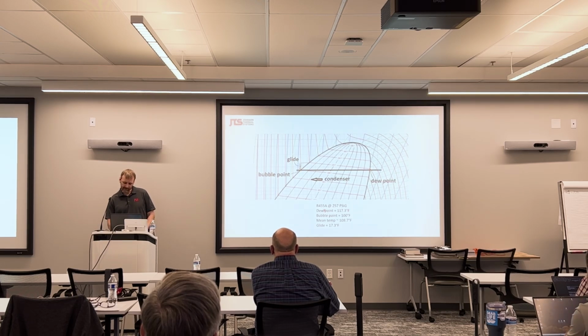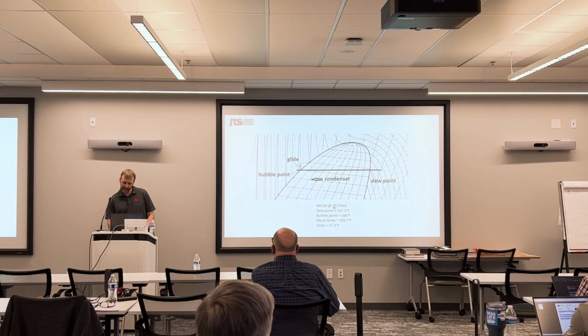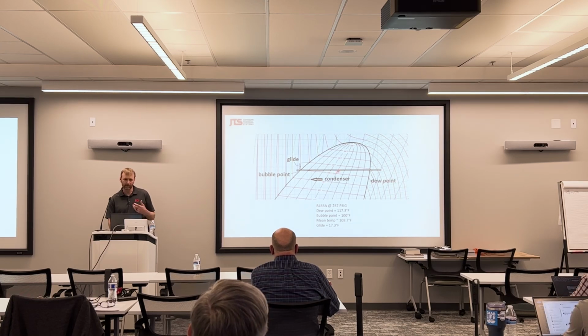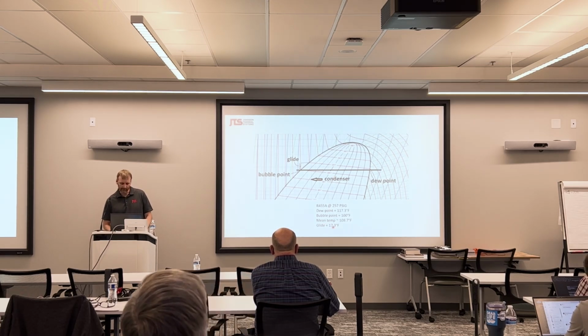In this case, with our 455A at 257 psi, our dew point is 117 degrees, our bubble point is 100 degrees, and our mean temperature is about 108 degrees. Your mean temperature would be your average or midpoint temperature. Our 455A in this application has about 17.3 degrees of glide. Pretty substantial.